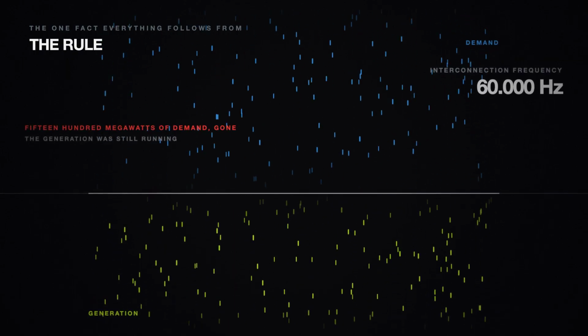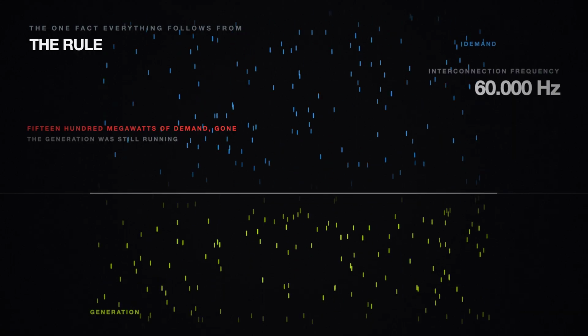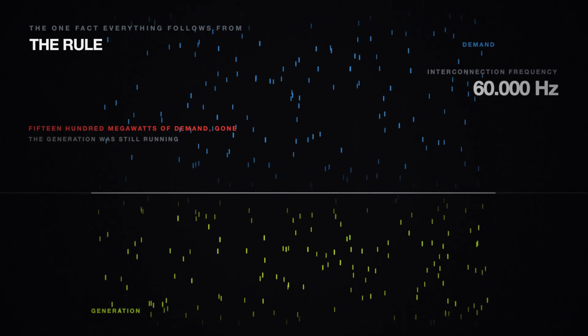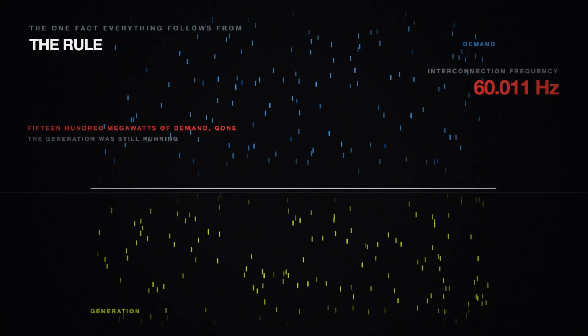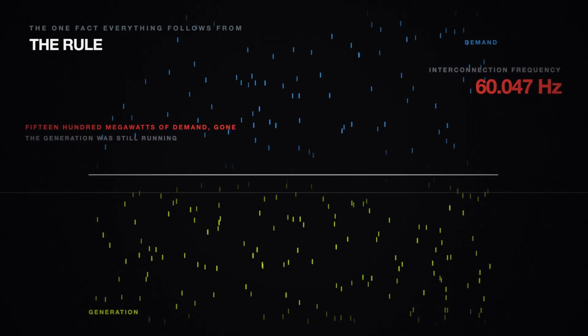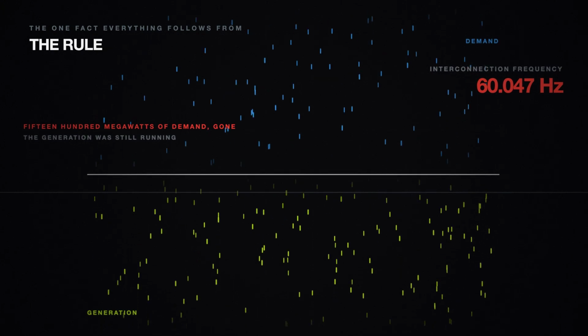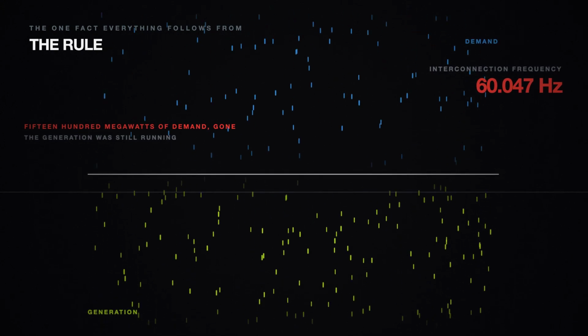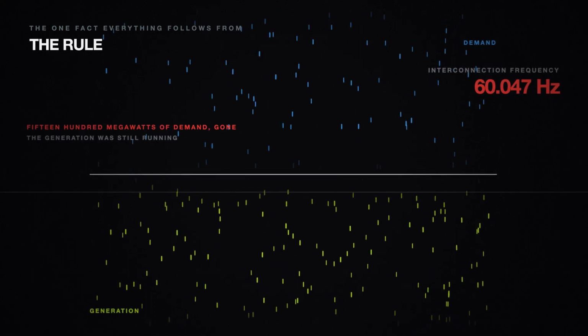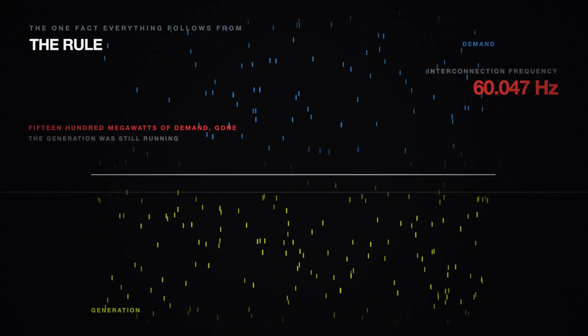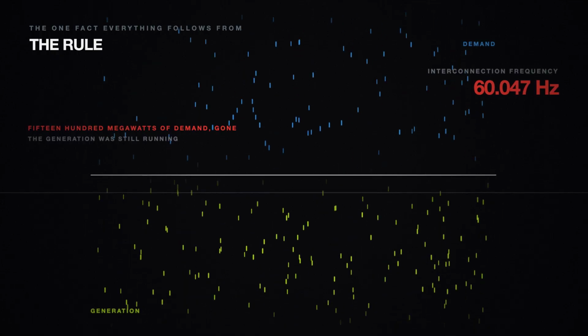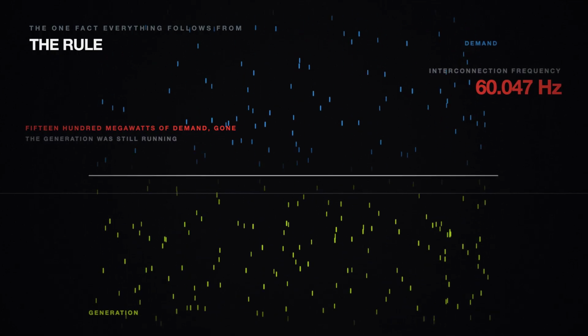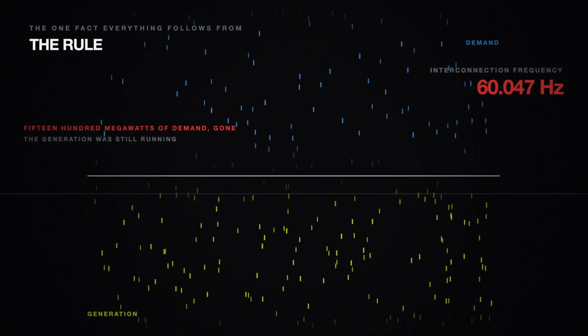1,500 megawatts of demand left in 82 seconds. The generation was still running. It had nowhere to go. So the needle went the other way, to 60.047 hertz, and voltage climbed to 7% above nominal. Operators spent that evening switching capacitor banks out of service, removing support from a grid that suddenly had too much.